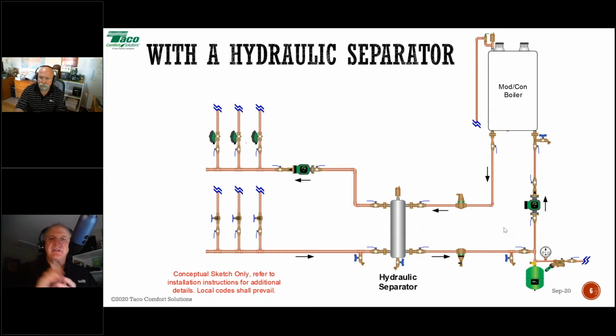What the vent on top of the hydraulic separator does, and we're presuming a hydraulic separator, it's just a big cylinder, is this. What happens in there is that the fluid's velocity drops well below 2 feet per second inside that cylinder. And when the water velocity in a system drops well below 2 feet per second, dissolved gases have a tendency to come out of solution. It's what happens in a scoop. Same thing happens in a scoop. But when they come out of solution, we don't want them being pumped into the rest of the system. Then we have that vent there that allows it to come out.